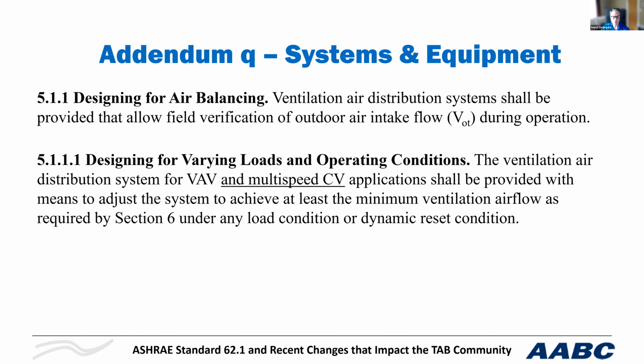Because as the supply air turns down, the mixing box, for example, is going to be less negative, which is going to have problems bringing in more outside air. So you have to open up the outside damper more to compensate for that lower mixed air pressure capability. So all systems are pretty much acting as VAV systems, whether they have a terminal box or not, and they need to be balanced as such. Another important thing to note is, of course, this is going to affect room air distribution too. As you're turning down the supply air, some diffusers may dump, and you're not having the air changes that you would normally. We talk about air changes during COVID and everything else. So it's another thing to consider.